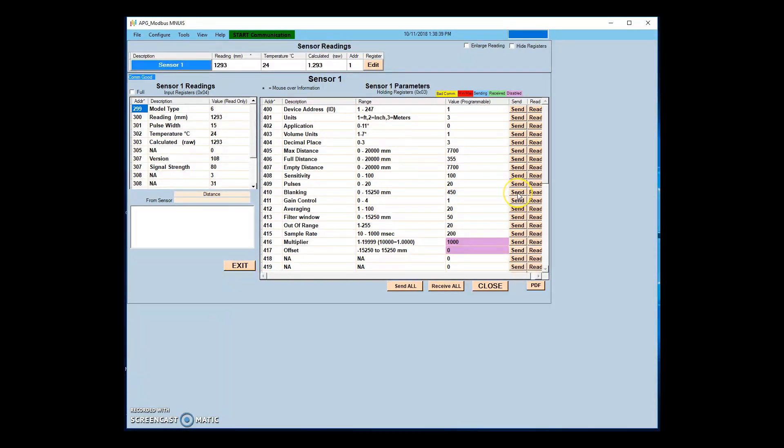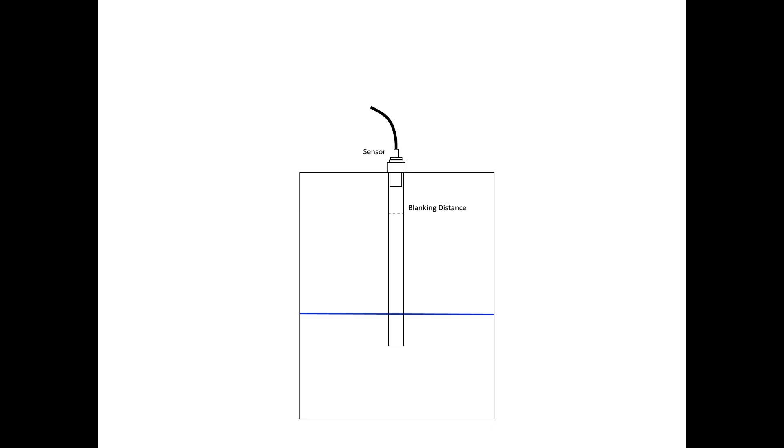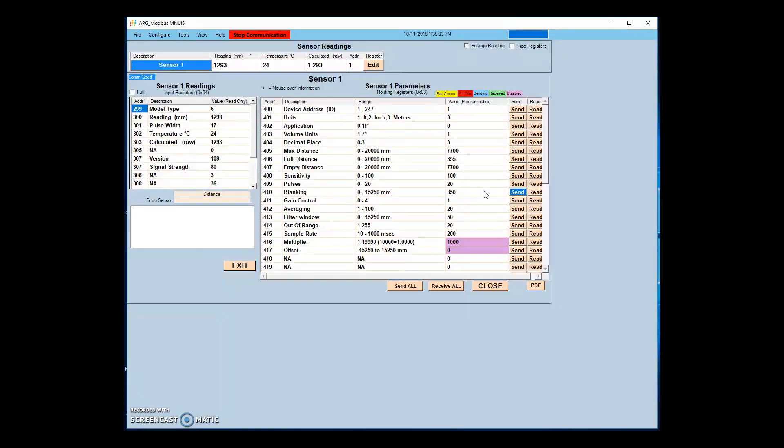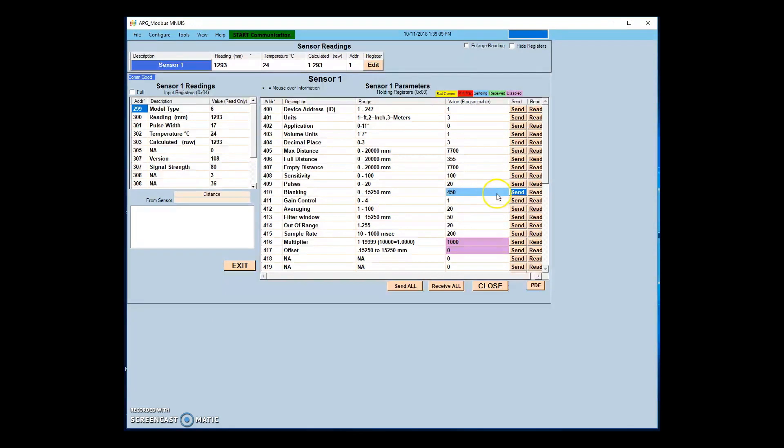Blanking distance is the distance from the zero point of the sensor from which the first echo will be accepted. Blanking distance is commonly used to reduce noise in installations involving a standpipe. It can also be used to ignore unwanted targets between the sensor and the closest target level. As pulse settings are increased, it may be necessary to increase the blanking distance to reduce multiple echoes.